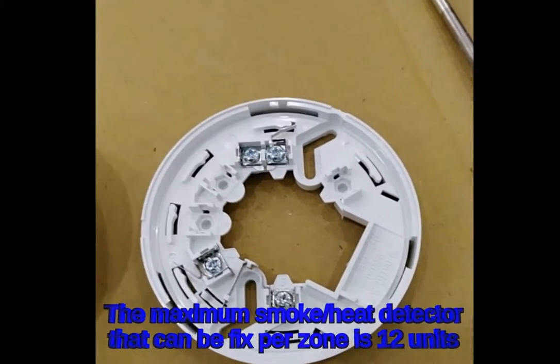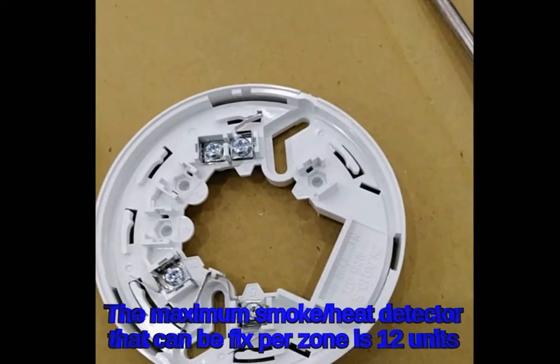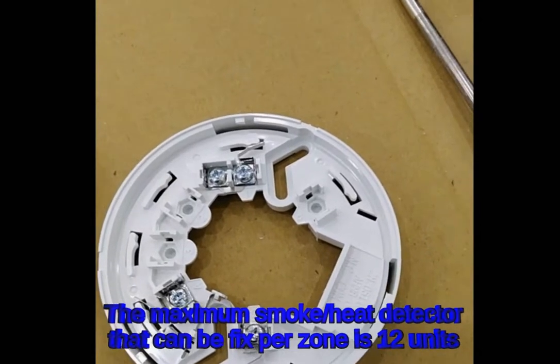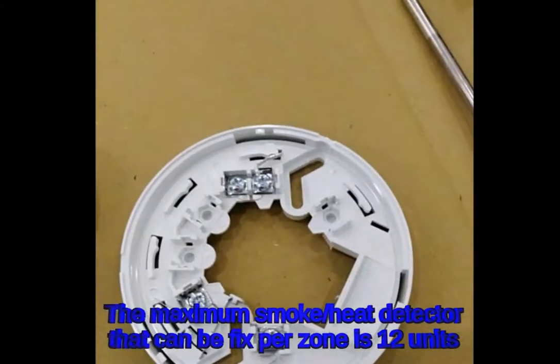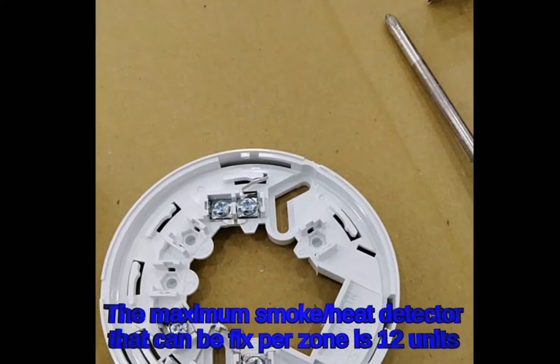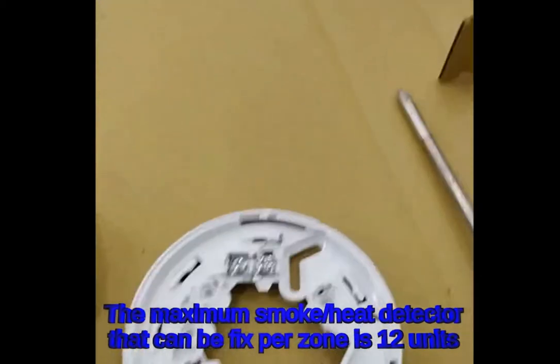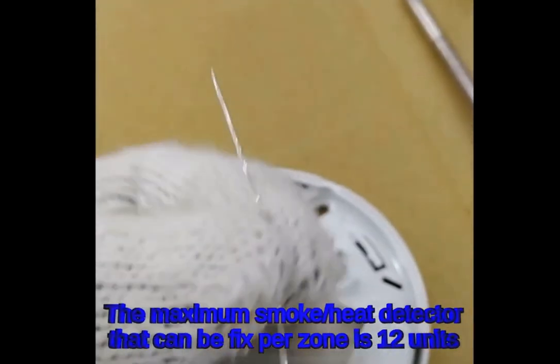At the last unit of the smoke detector or heat detector, we are going to fix the end-of-line resistor. The resistor is provided when you buy the panel for the fire alarm. The number of resistors depends on how many zones you have — here we have only one zone, so one resistor is provided. In this project there are eight smoke detectors, so at the eighth smoke detector we will be fixing this end-of-line resistor.